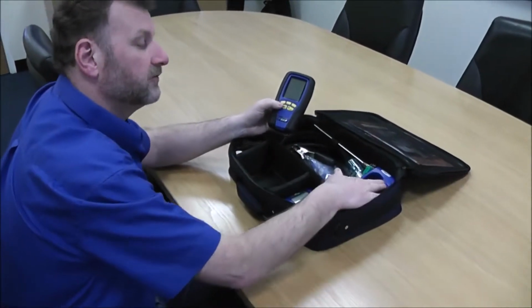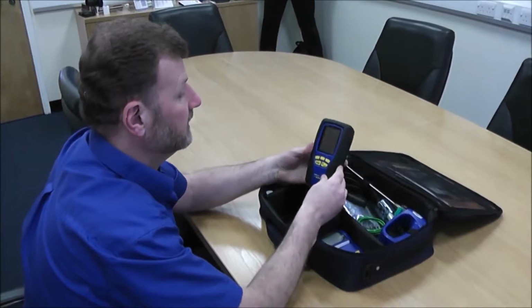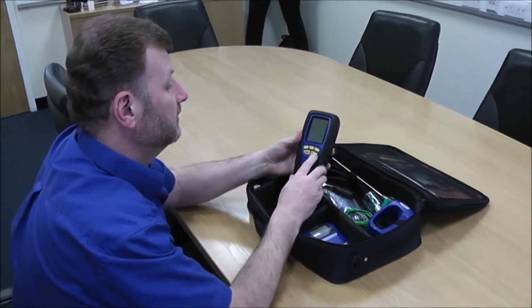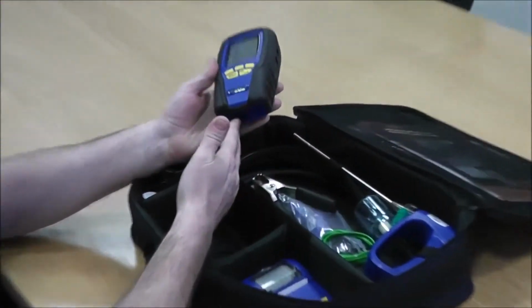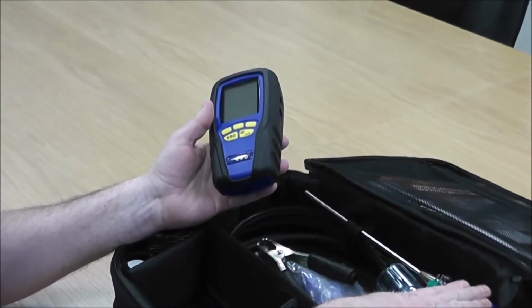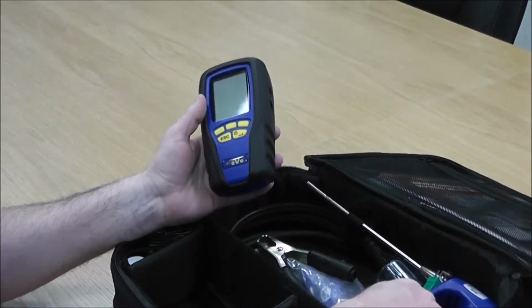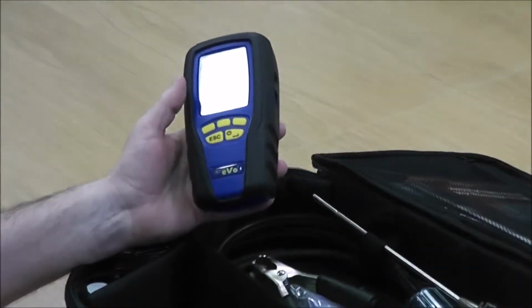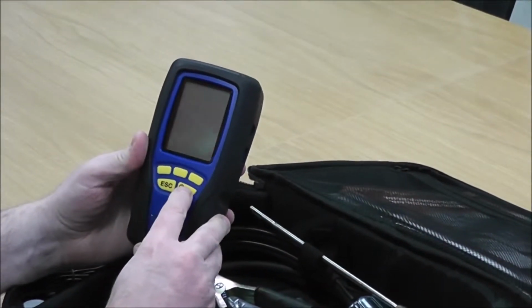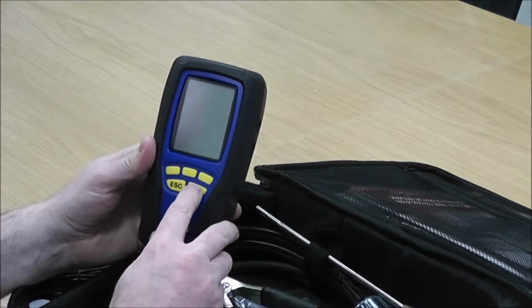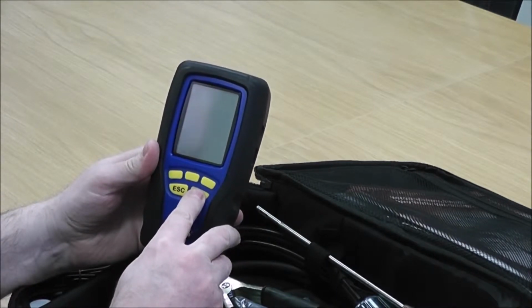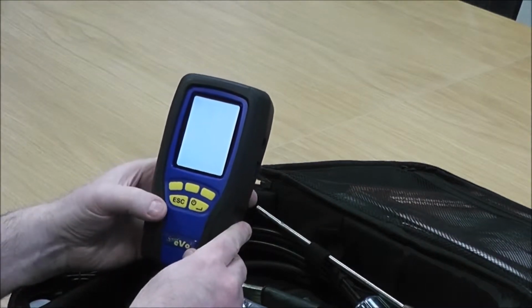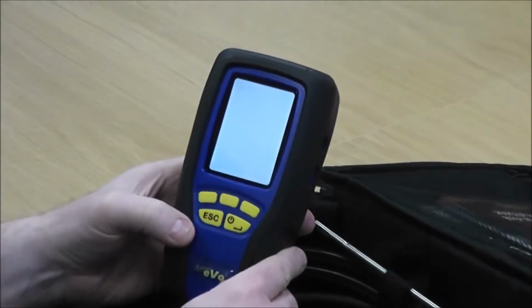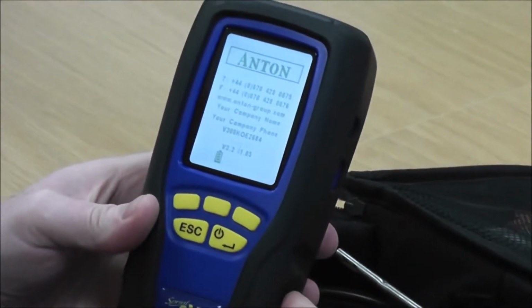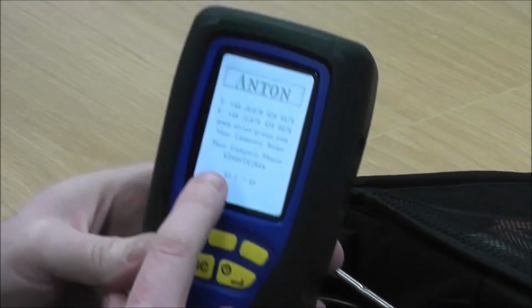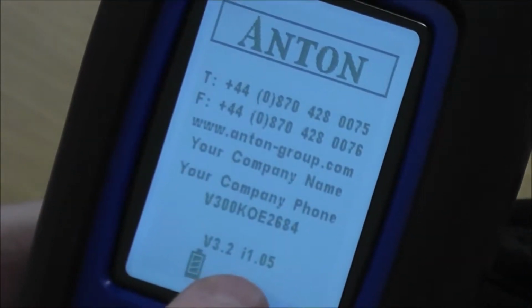Okay, we've done the flue probe. Now we're going to concentrate on the analyser itself, doing a couple of checks on the analyser. Normally you turn the analyser on with your flue probe connected, and you'd be outside, standing with your instrument and your flue probe, or you'd at least be hanging your flue probe out the window. But I'm just going to do instrument only at the moment, just to show you some checks. So we turn the instrument on. This is a Sprint eVo. When you see it first comes up, you'll see on the screen it's starting up.